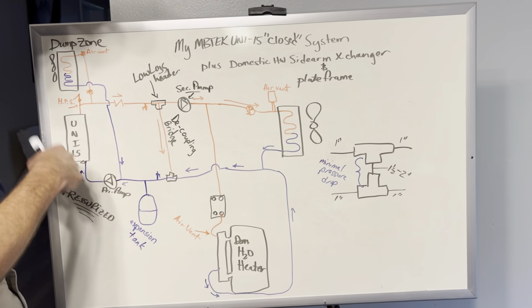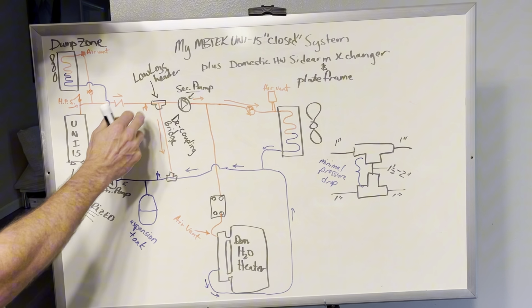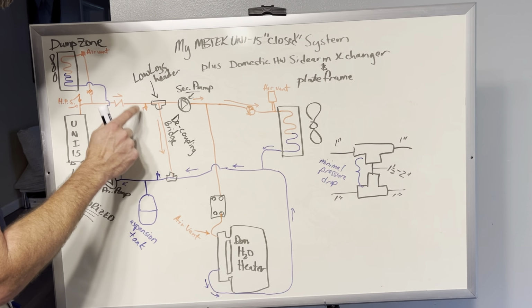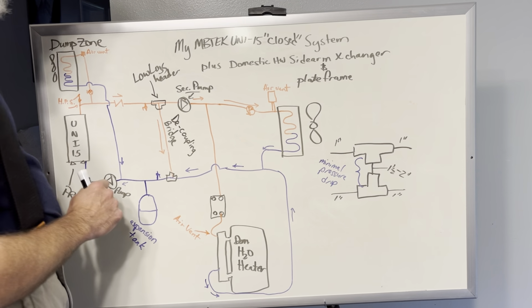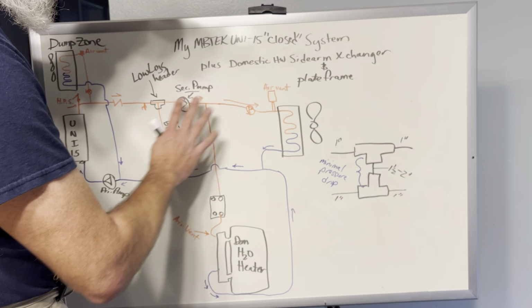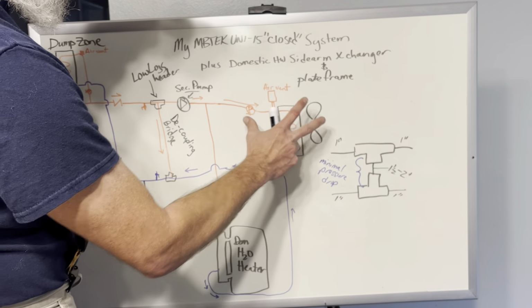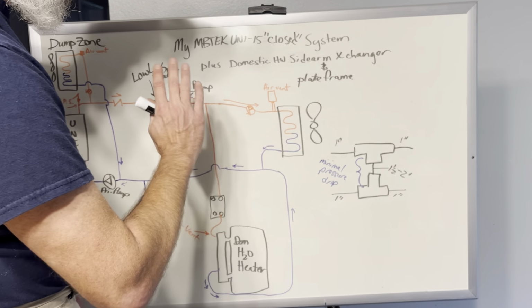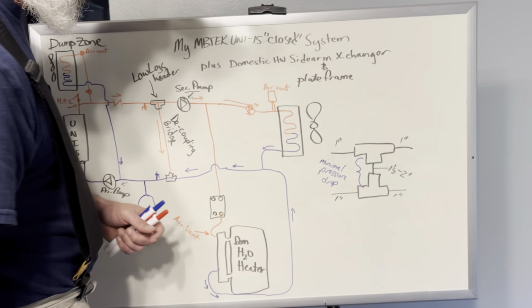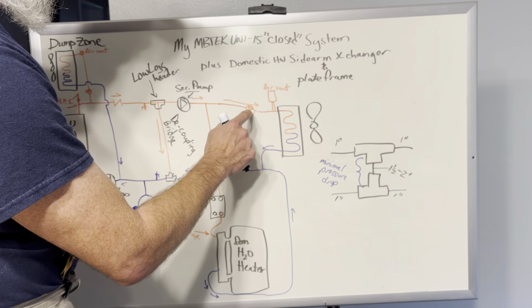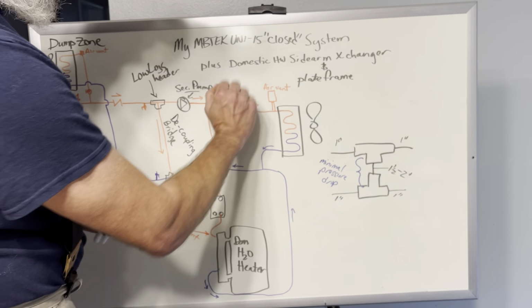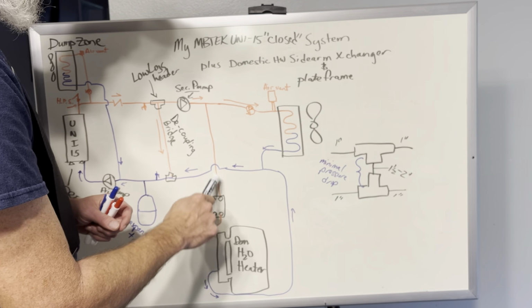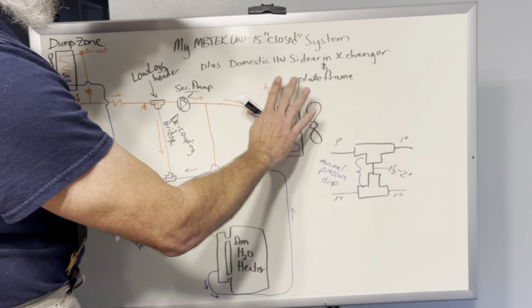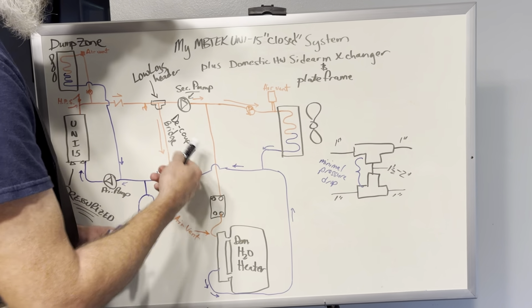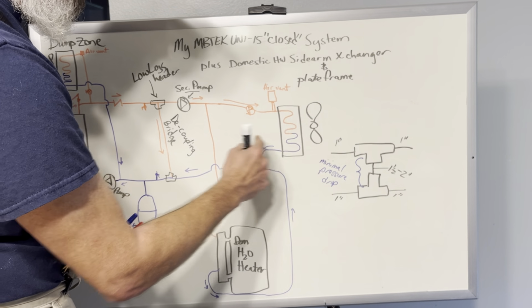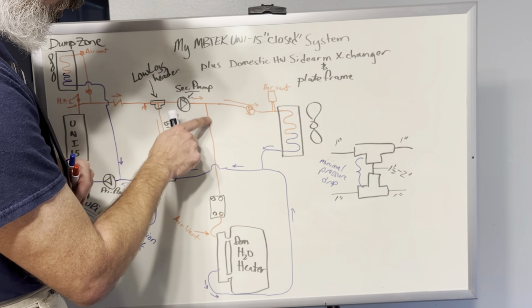Once the hot water from the boiler has made it to this point, it's measuring temperature right here. Once this water gets warm enough, that pump is going to come on and start moving water on this side. If my house is not calling for heat, the thermostat is not going to be saying I need heat, and it's not going to bring my blower on. This valve, a 120 volt valve right here, will be closed, so water can only go this direction right now. What I'm getting ready to talk about is a no heat situation, where I'm just heating domestic water. There's no flow going through that coil heat exchanger, which is a water to air heat exchanger. Water will only be going here.